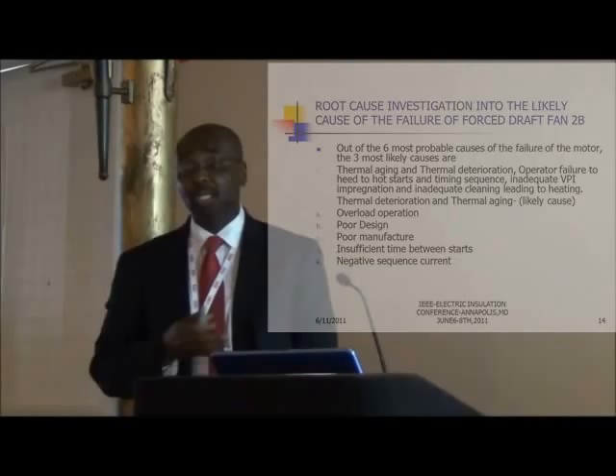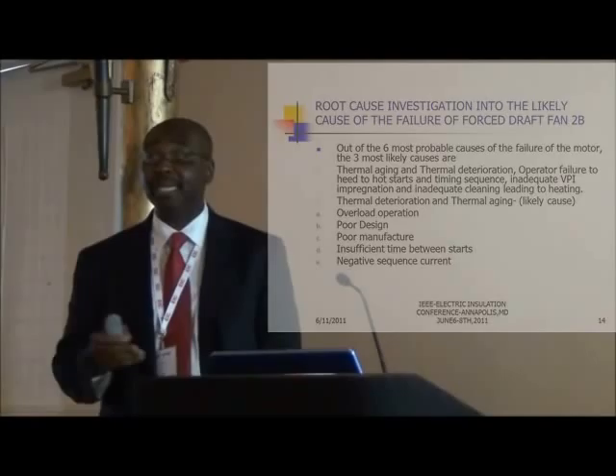Poor manufacturing can also be a factor. If the ground wall insulation is not properly optimized for electrical stress and temperature, it can lead to high temperatures and ultimately insulation failure. Also, insufficient time between starts is critical. Most large motors have two cold starts and one hot start allowed. The timing between these starts must be adhered to, because starting a motor creates five to six times the normal full load current.